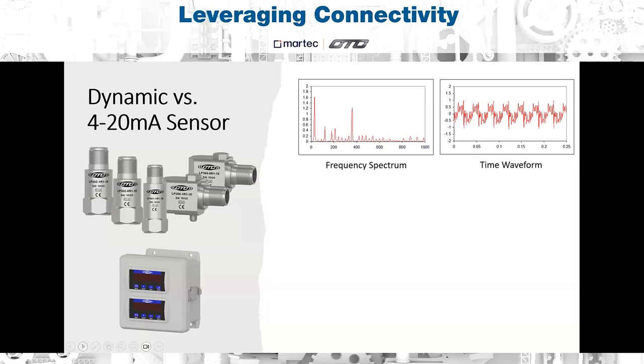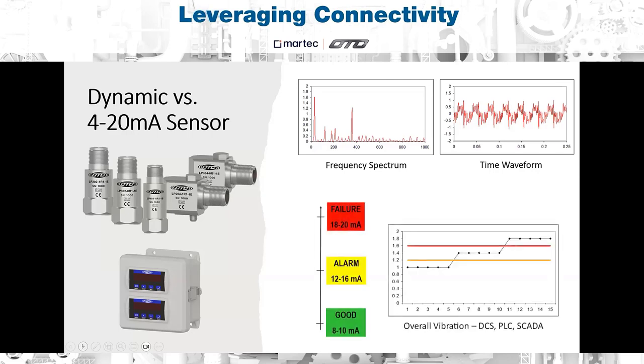For these cases, a 4 to 20 milliamp sensor can also be utilized. Basically, a 4 to 20 milliamp sensor is a sensor that provides a single output ranging from 4 milliamps to 20 milliamps, and that output is proportional to the amplitude of vibration in a machine. These sensors can tell you the level of vibration. However, they cannot be used to actually analyze or diagnose the issue. The 4 to 20 milliamp signal sensor can also be used to configure alarm levels to either show warning messages or completely shut down the machine if the vibration raises to a certain level. These are a good preventative measure for monitoring equipment and preventing any unplanned downtime.